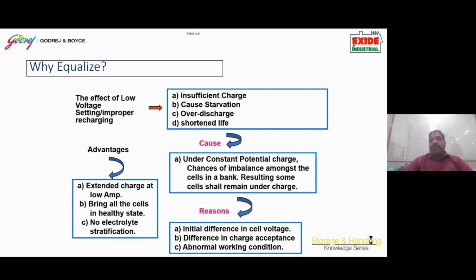Electrolyte stratification is something like, the electrolyte inside the cell tends to have a non-homogeneous kind of behavior. That means if you top up the electrolyte, normally the H2SO4 should mix with the water. But in some cases, in standby applications, where the electrolyte is in a state of constant float, this mixing does not happen. So you see that there is a density difference. When you measure the density on the top, there will be more water. And when you insert the hydrometer deep into the bottom of the cell and measure the gravity there, the gravity will be different. It will be more. So this kind of pattern is called electrolyte stratification.